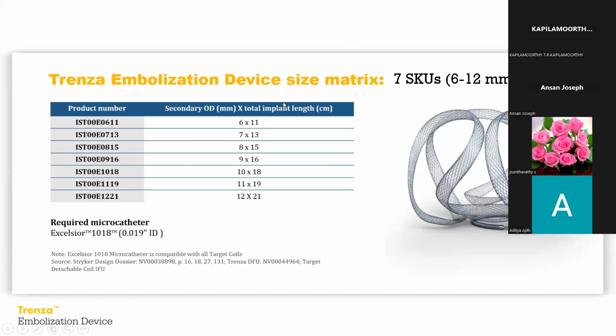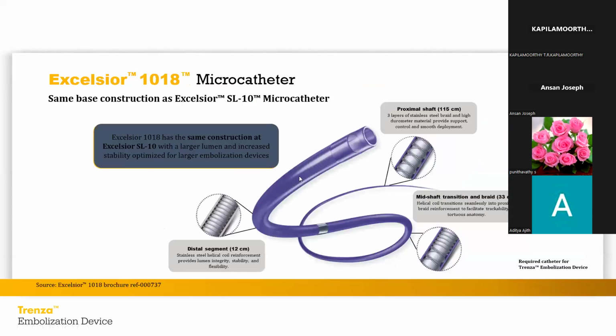The available sizes are 6 to 12, with a fixed length in each subgroup. So totally 7 available lengths are there. It is delivered through the Excelsior 1018 catheter, which has a 0.019 ID. It is 0.002 ID bigger than the normally used coiling catheters. Similar to any other coiling catheter, it has two markers with additional support for the delivery of the system.